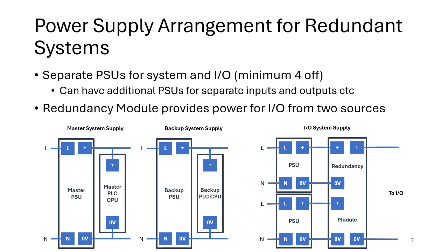And effectively what's inside that redundancy module is a set of diodes, or maybe MOSFET technology, but what it's doing is it's isolating the two power supplies but allowing whichever power supply is dominant to provide power to the I/O. But if any one of those power supplies fails, then it allows the other power supply to take that power and supply it to the I/O instead. So we need more power supplies, typically four, two for the system and two for the I/O system supply. And then we also need that additional redundancy module as well. So now we're up to at least 5 components, but you might also want additional components again to segregate inputs and outputs, and maybe even more if you want to segregate analogs and discretes, as we said before.